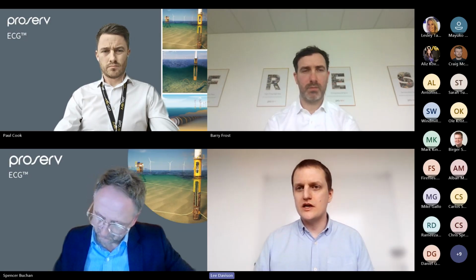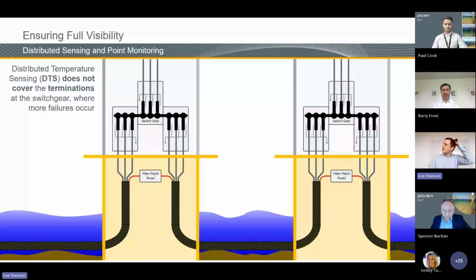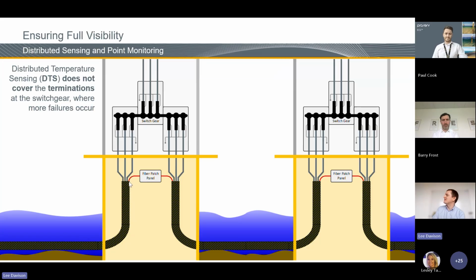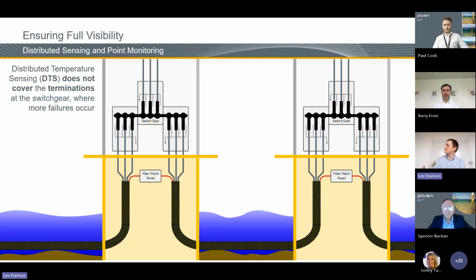I'm just going to share my screen, because the extra piece that we bring to a holistic, complete monitoring solution is as good as DTS and DAS are. Excuse my out of scale sketch, but hopefully you can see this is a transition piece at the bottom of the turbine. You've got your array cable coming in. The power conductors go off to the switchgear, and the fiber bundle goes off to a telecoms patch cable or patch cassette somewhere. Because the distributed sensing systems are based on the fiber optic, you're not actually getting any visibility of the terminations, which are depicted up here.